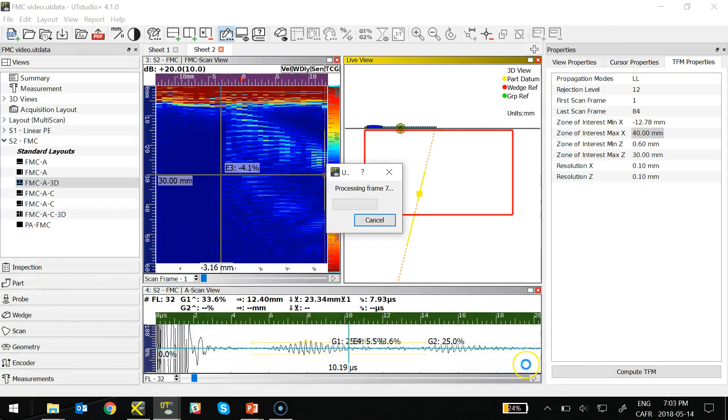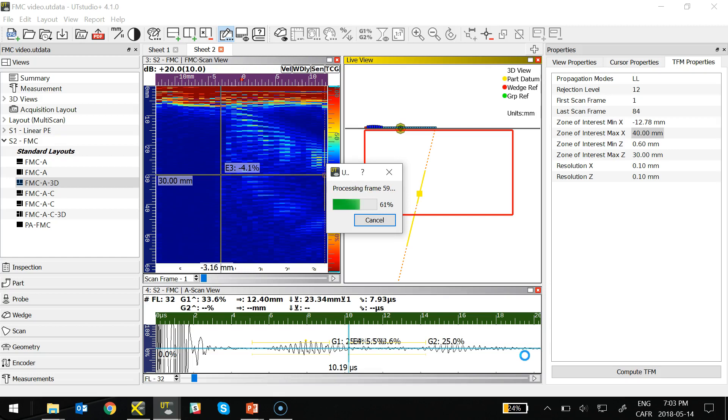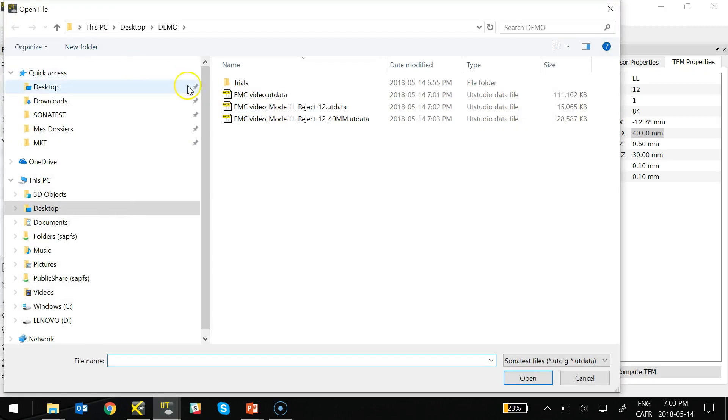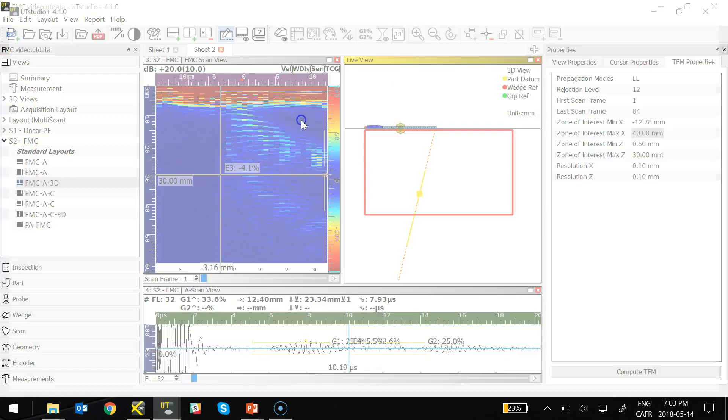So now using the same FMC scan information that I previously recorded using the VeoPlus, I'm able to compute a new TFM image set using UT Studio Plus, but now over a different zone. I could do the same thing using different algorithms or propagation modes, for example.